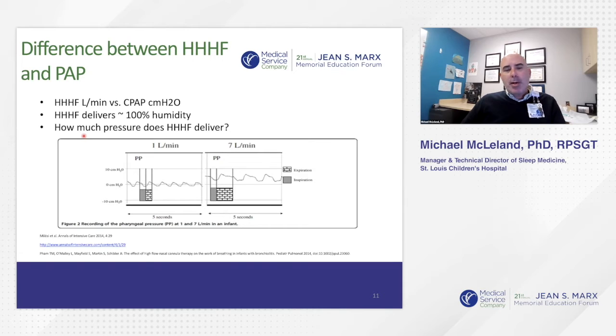The reason it's so hard to measure is because CPAP is more of a closed system - it covers the nose and/or mouth depending on the mask, and we try to limit the leak around the mask, with a built-in leak we can measure. High flow is only meant to take up no more than 50% of the space in the nares, and the patient can also breathe through their mouth.